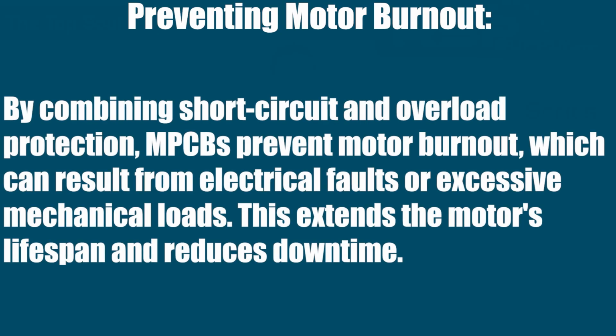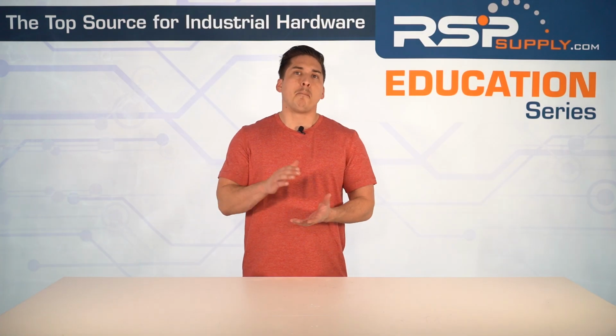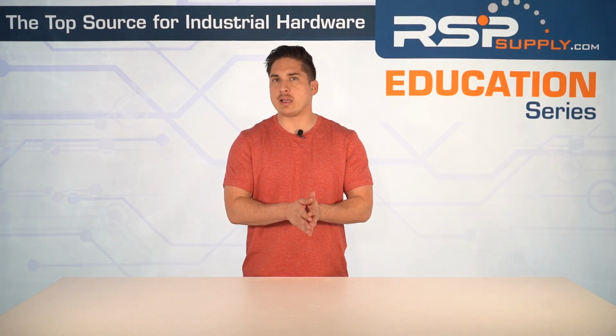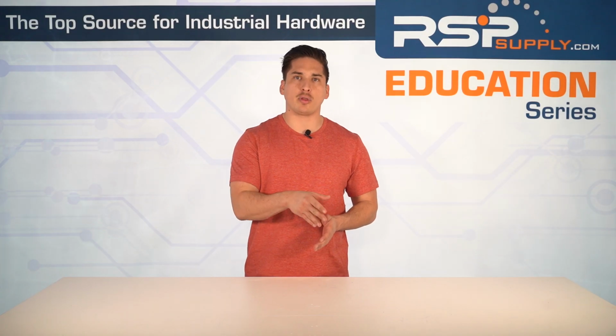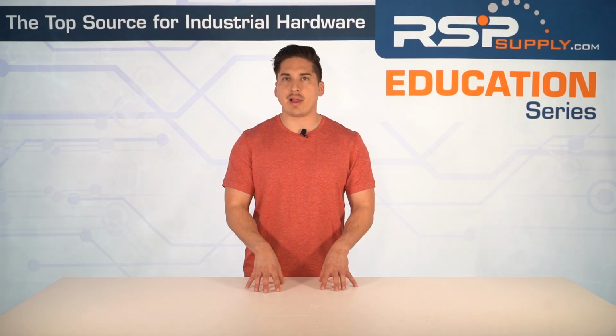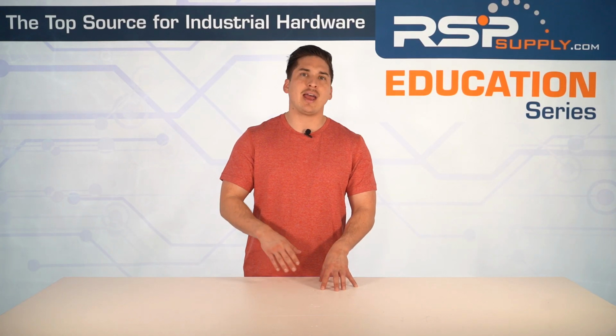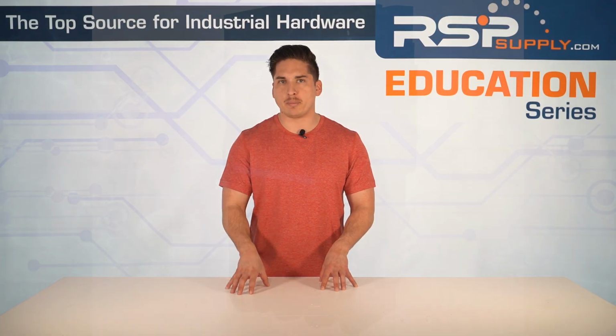They prevent motor burnout. By combining short circuit and overload protection, MPCBs prevent motor burnout, which can result from electrical faults or excessive mechanical loads. This extends, in turn, the motor's lifespan and reduces downtime. So in summary, motor protection circuit breakers are critical components in industrial automation, providing robust protection for motors specifically by addressing both short circuit and overload conditions. They enhance system reliability, they prevent equipment damage, and they ensure efficient operation of motor-driven processes.